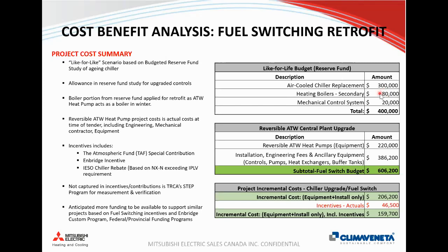And that was included in this because the heat pump will act as a boiler to a certain extent. So that was included from the condo corporation's point of view. And they also had a line item for mechanical control system, which was required to control the heat pumps, control the staging, and control the auxiliary boiler, and to tell who to do what at any given moment in time.